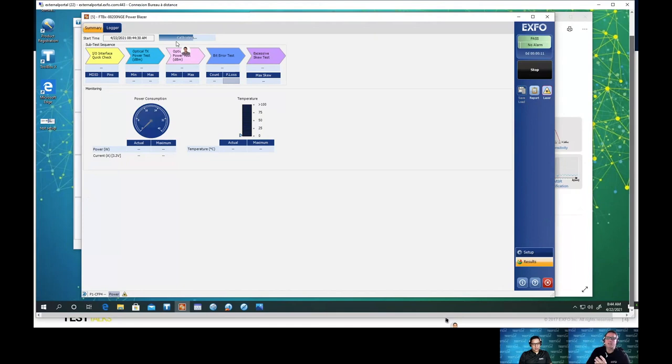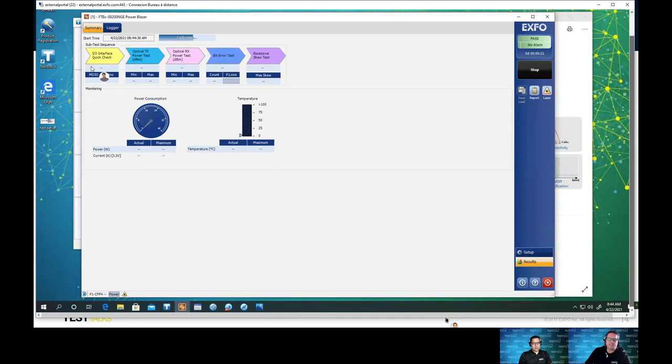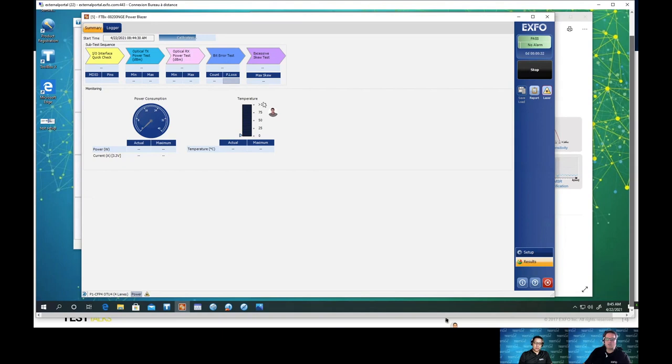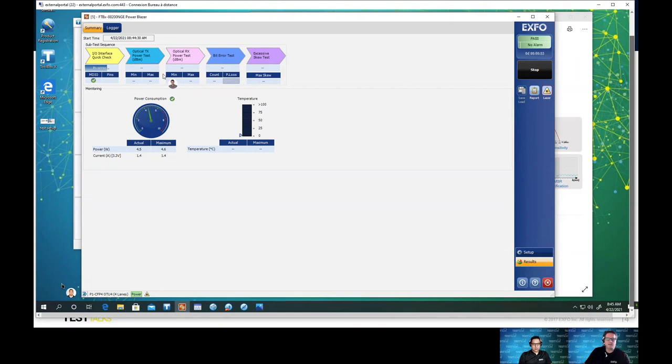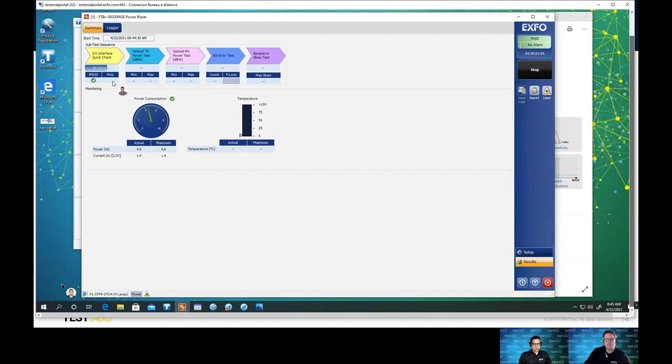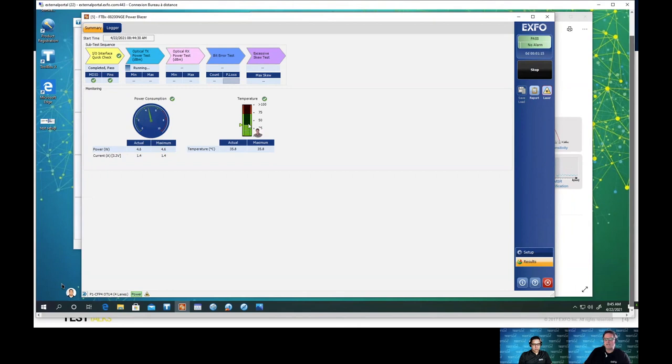This setup is based in Quebec City. And if you want to know more and have a personal demo, we can always do this demo again for you. My first test will be the iOptics. iOptics is developed by EXFO. It's a program that is testing and validating the transceivers. The first thing it does, it does an MDIO validation or I2C. It's a quick check on the electrical level. Then it does an optical transceiver level and stability test. It does the same thing for the receiver, level and stability. You can see minimum and maximum. It will do a bit error rate test and will monitor power and temperature. I'll jump to the demo.